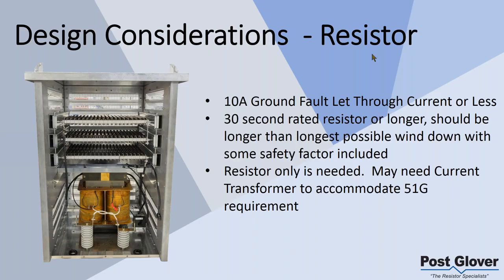Now, the high resistance ground, as I show right here, is more likely to be usually 10 amps. It doesn't have to be 10 amps. It can be 5 to 10 amps, but most of the time we see 10, just because it makes it easier in terms of capacitive charge current. It's likely that it'll be much less than that, but it takes that out of the consideration. Usually you want a longer rated resistor. Doesn't mean you have to have one, but just keep this in mind.